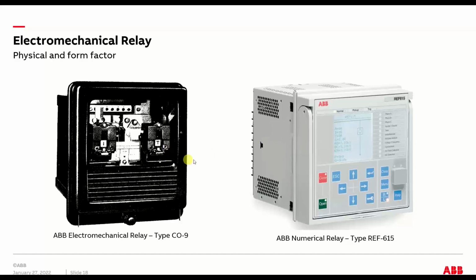This is just a follow through on the original concept, because it worked. This was a good design. It worked well, and it was copied over and brought forward into the new technology. But this relay here can do overcurrent 50/51 on a single phase. That's it. So on a normal three-phase breaker, you'd have one of these for each phase, A, B, and C. This guy does all three phases, plus almost any other thing you can ask it to do. So a panel that might have had four or sometimes even six or nine of these devices on it for one breaker has now been reduced to a single box.